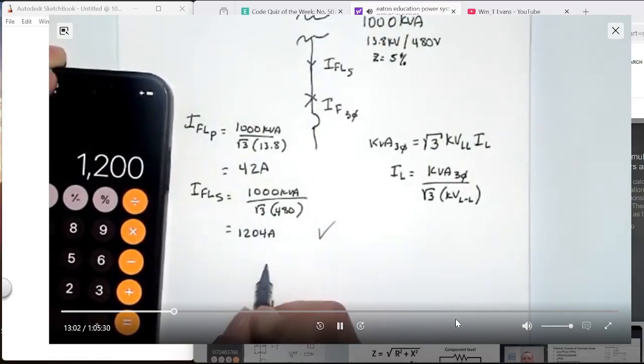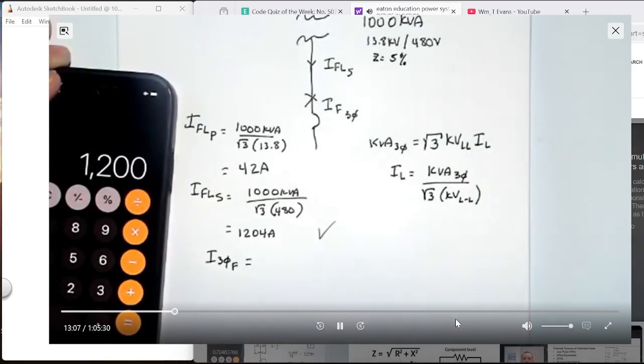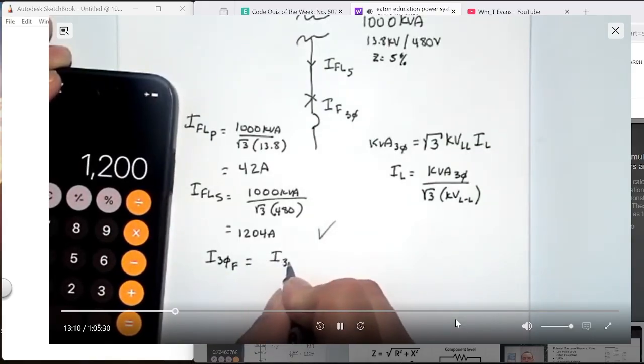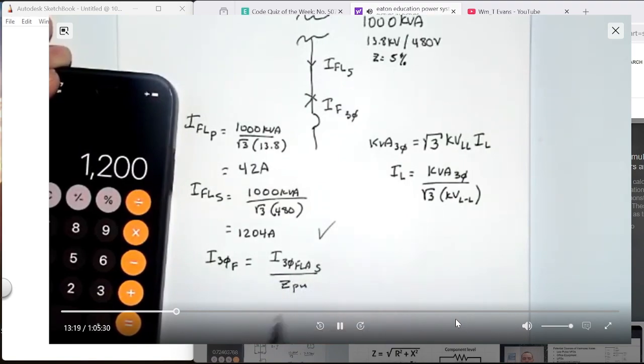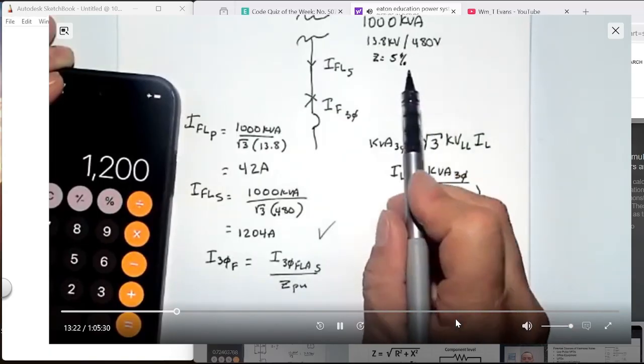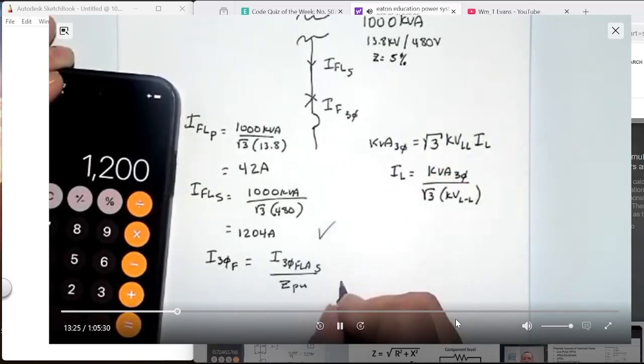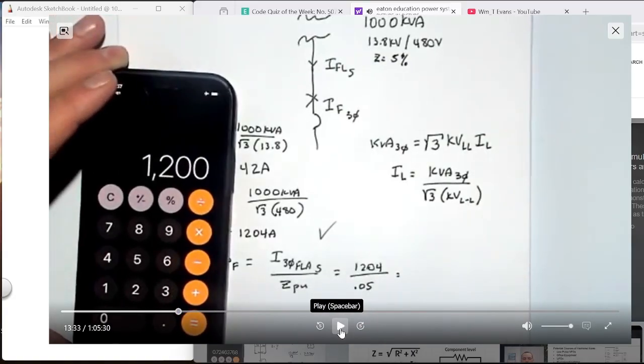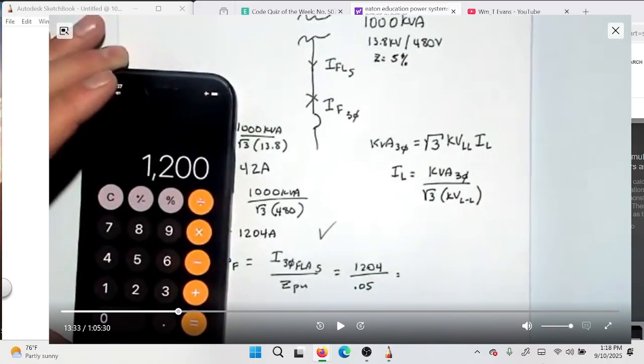So if I want to calculate my three-phase fault current, it's actually very simple. All we do is we take the three-phase full load amps on the secondary, divided by the impedance in per unit. And we'll talk about what that means. Basically, per unit at 5%, per unit is 0.05. So we take 1204 divided by 0.05, and we get... Got that? That's how you get your fault current.